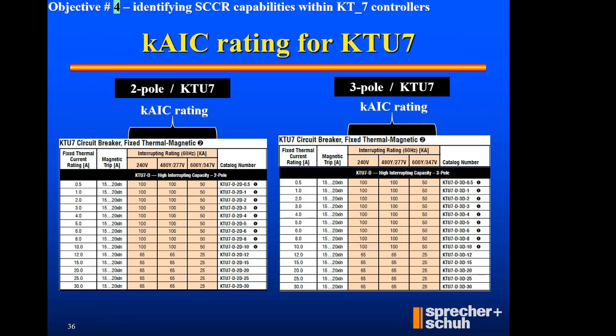Taking it one step further, just to cover KAIC on that last controller for KTU7, right on the selection page of the 2-pole device or the 3-pole device, we've got the capability of getting up to 100 KAIC on those lower 100% rated devices. That's what this footnote is. Footnote says these are 100% rated. These other 12 amp and larger are 80% rated, just like a regular circuit breaker. But agreed, I can get 100 KAIC on those 100% rated devices, or I can get 65 KAIC on those 80% devices, just like the regular circuit breaker. So again, that's on the actual selection page of the KTU7.